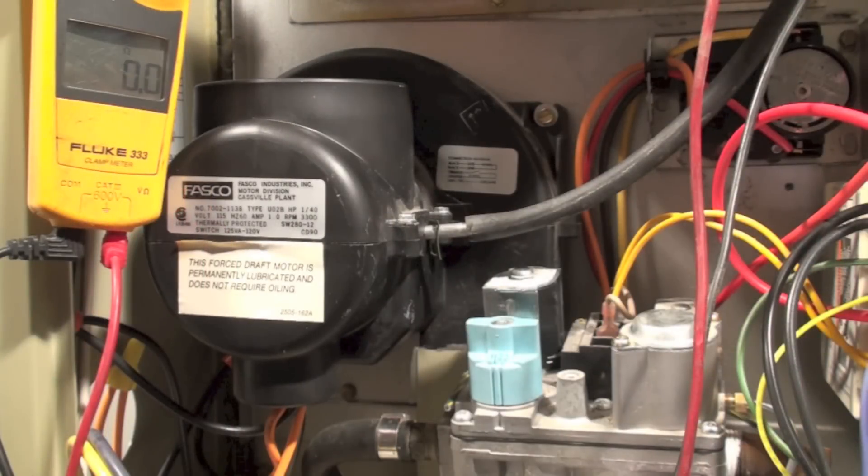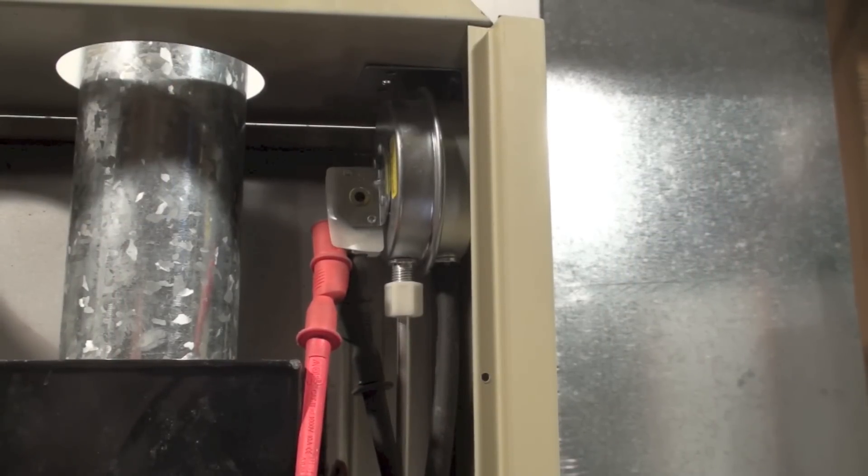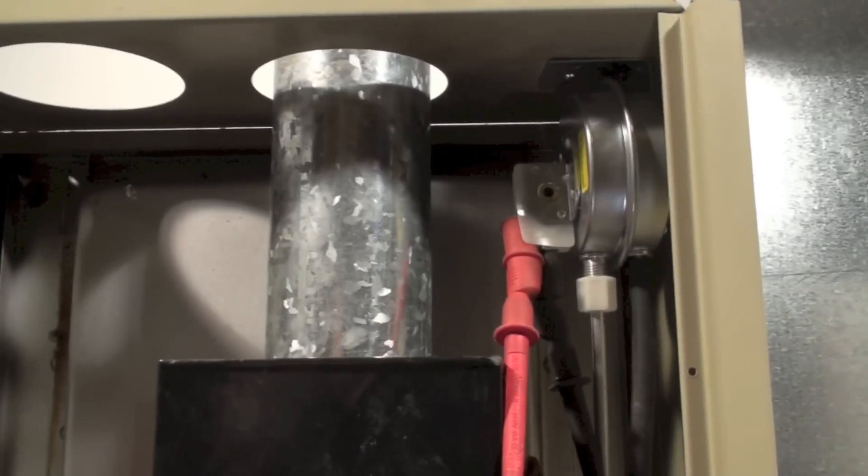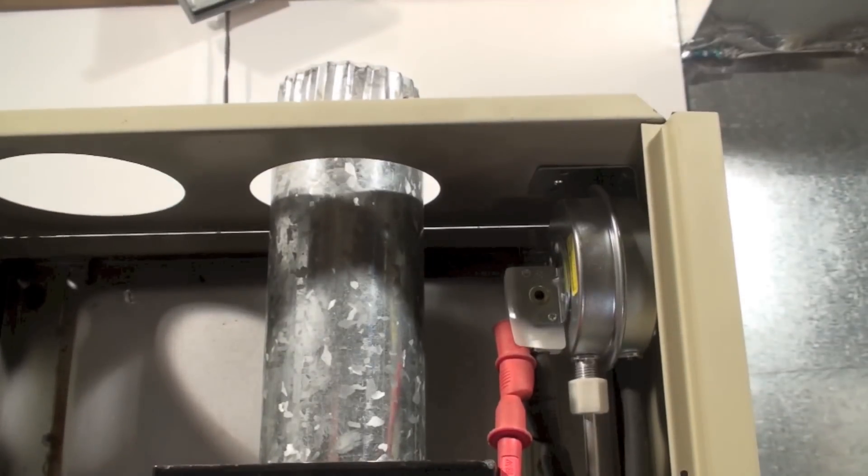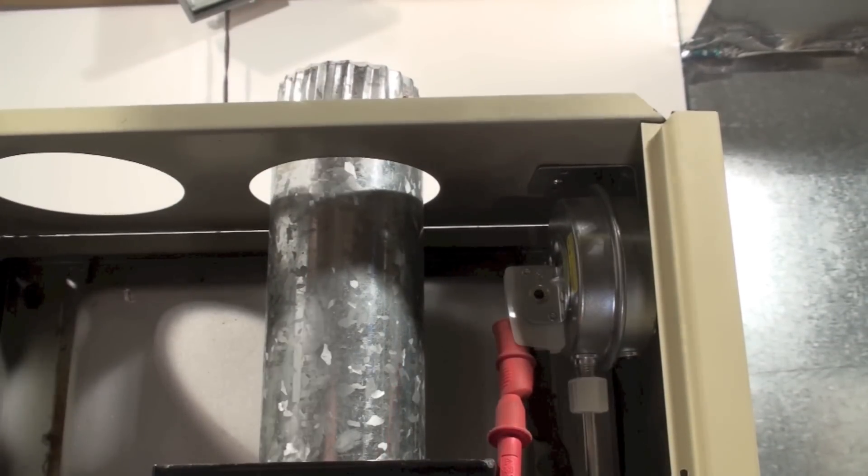I've got this thing started up, the inducer's running, and I've got a meter across the pressure switch so we can see what would cause this pressure switch to open. Normally this thing is normally closed.